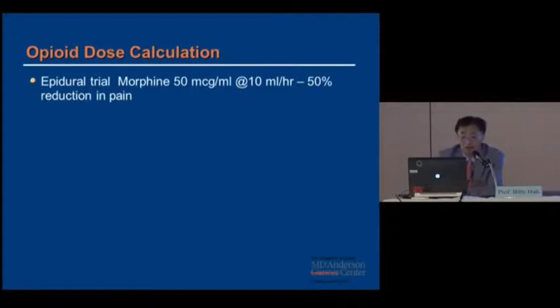One thing you need to know: once you decide on the concentration of drug, there's a lowest limit to how much you can give—there's a limit to the lowest dose the pump can infuse. The first factor is 20. If you pick, say, the 10 milligram per ml concentration of morphine, the lowest amount you can infuse is that divided by 20, which is 0.5 milligram per day. If the patient has a profound side effect at 0.5 milligram per day, you have to change the concentration. This factor of 20 is a number you really need to remember.